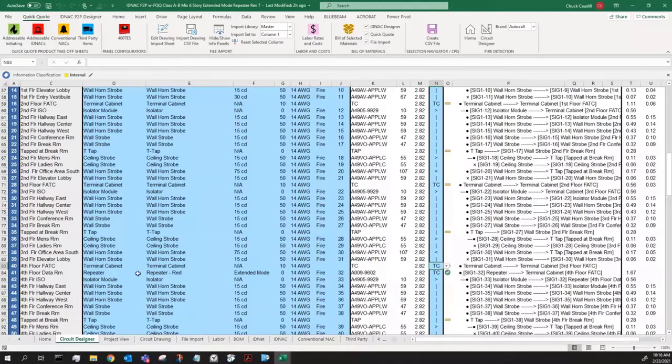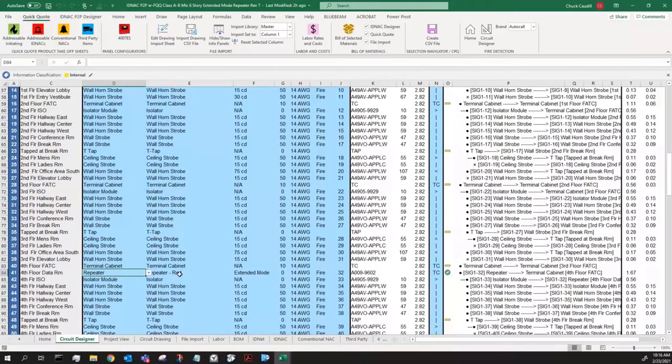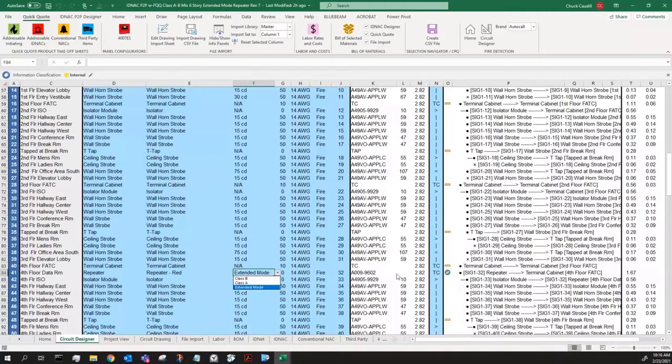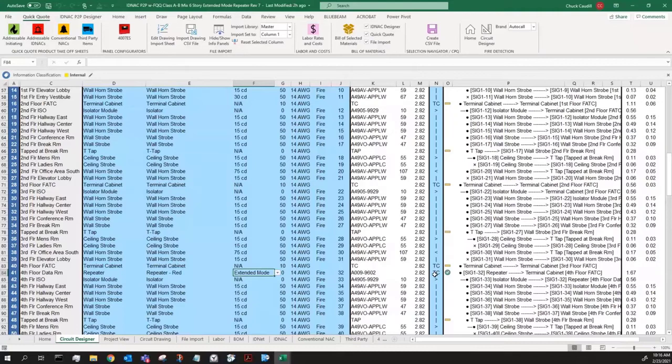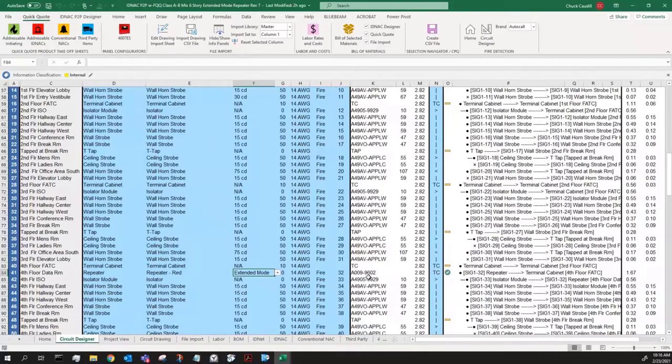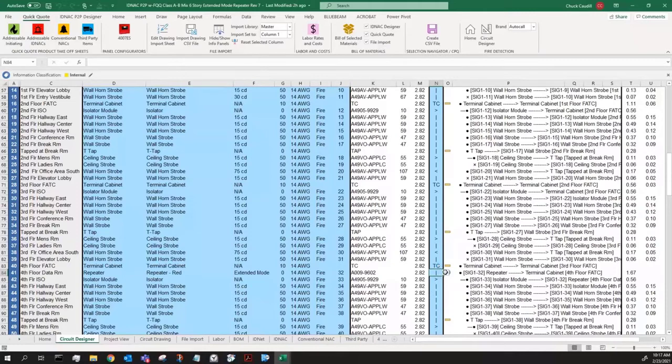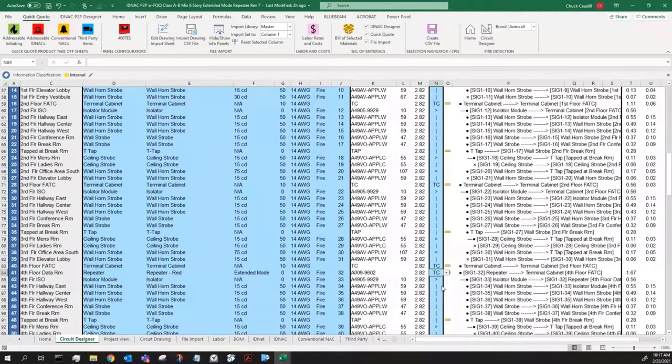Then I'm going to put a repeater in here, and I throw a repeater. Red or platinum, it doesn't matter. But what matters is what mode is it running in? Class B wouldn't work for me. Class A isn't really this mode. Extended mode is what we're looking for. What that does, that puts you in the middle of the Class A loop, and we're going to send power up to the next floor and down to the floor below as part of this Class A loop. So I put a repeater mode. I say tie to the terminal cabinet above me. I could have also just put a straight line in here because it is the next line up. But for continuity, I'm doing everything as tied to the terminal cabinet above.